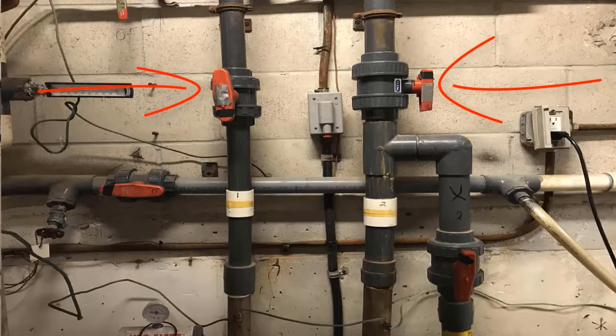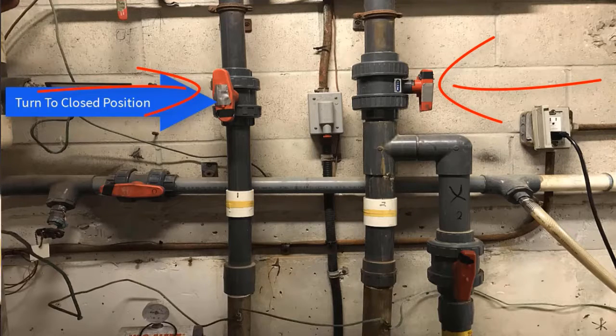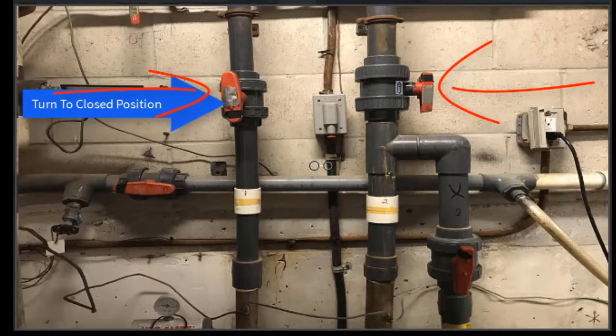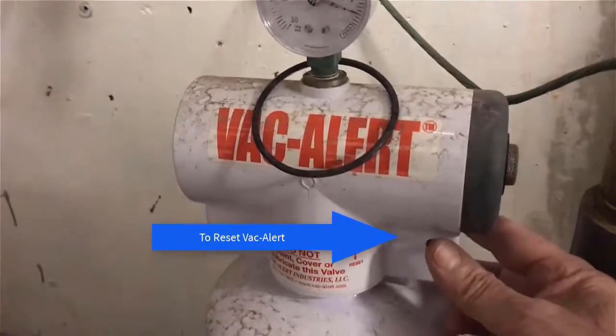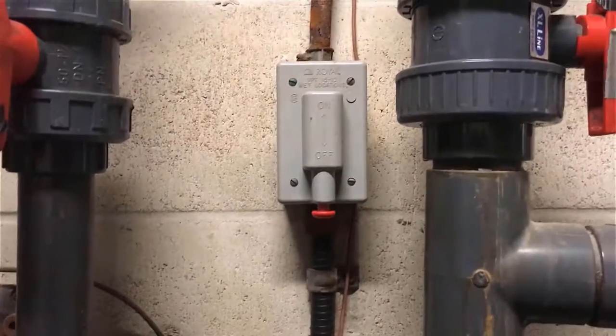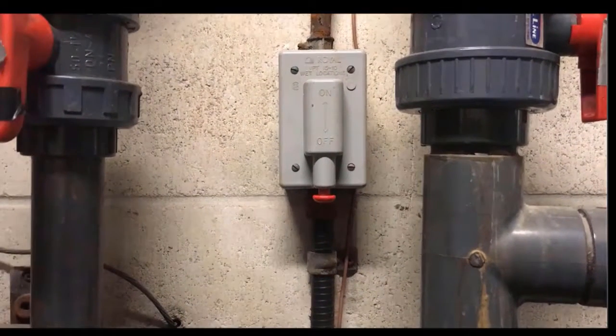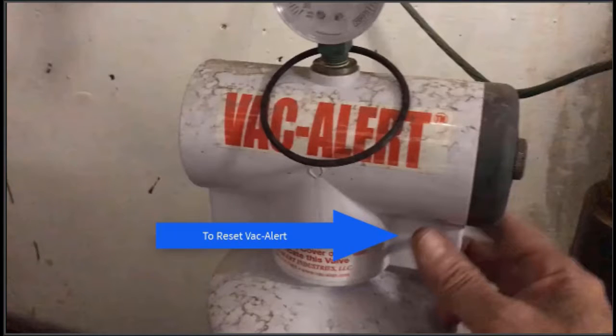There might be some point where the pool inspector asks you to test the pump, and you do that by first turning number 1 all the way when the spa's on, and then turning number 2 all the way, and then you'll hear a pop, and once the pool inspector says it's okay, then you can release it and turn the two valves back into the normal position. Before you turn valves 1 and 2 back into the normal position, after you do the vacuum release test, you should turn the pump off, and it makes it a lot easier. And then you can reset the vacuum pump like I showed you with that little red lever.